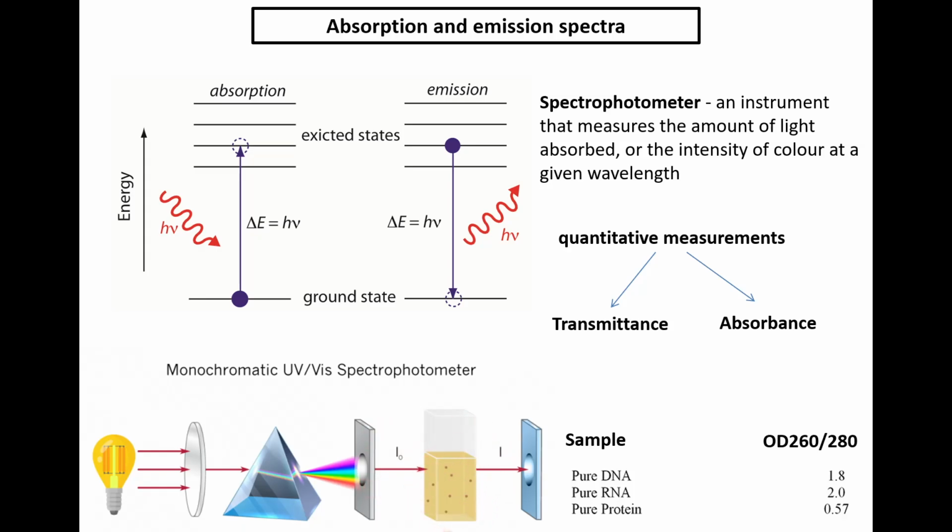Now, some amount of this wavelength will be absorbed by the substance, and the other light will be transmitted into a detector. From here we can quantify how much light is transmitted, because we know how much light was coming in and how much light is transmitted, so by this intensity ratio you can find out the transmittance. Then from the transmittance, the instrument will calculate the absorbance by this medium. So this is the overall general architecture of your UV-visible absorption spectroscopy.